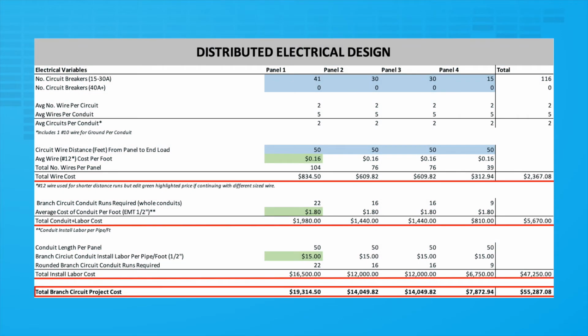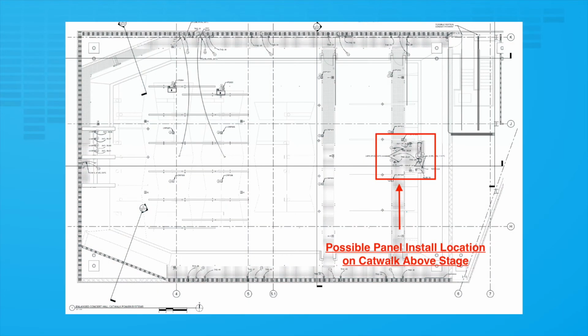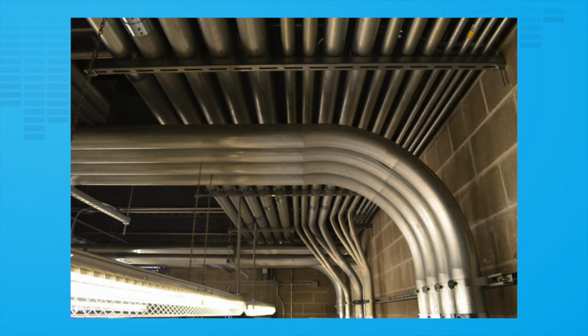For the distributed electrical design system, if you're able to utilize the narrow panel configuration and install the breaker panels only 50 feet away from the end loads on a nearby I-beam support or a similar surface, you will now only be running the 10 conduit and 94 individual wires a mere 50 feet instead of the full 200. The panel's service wire run will now take up the initial 150 feet, which typically only consists of a single conduit run that will house 5 wires for the panel's incoming service.